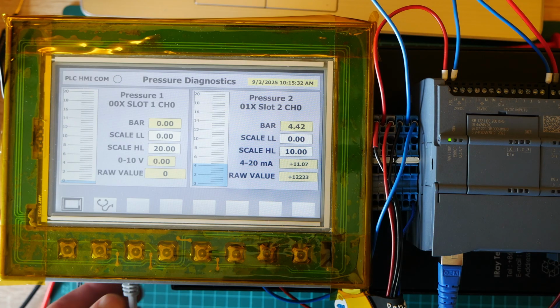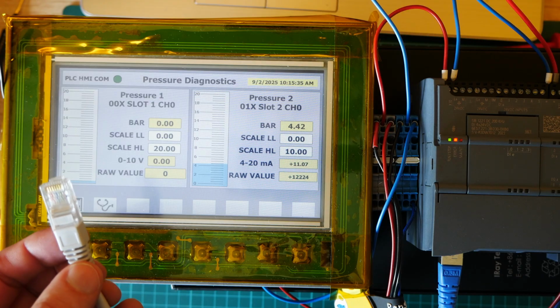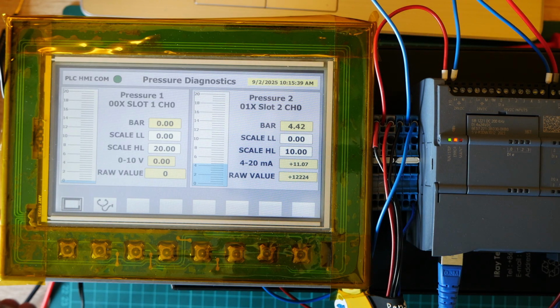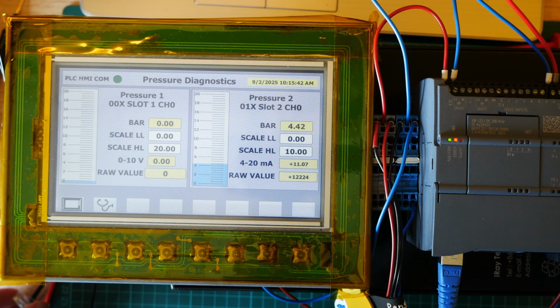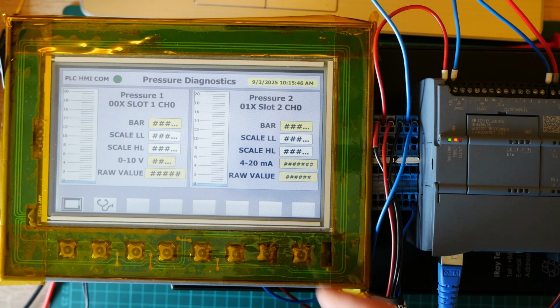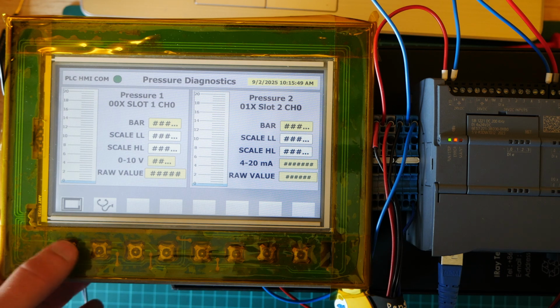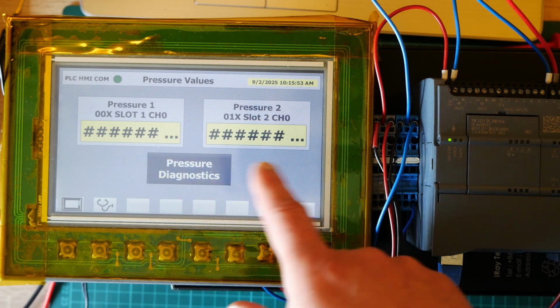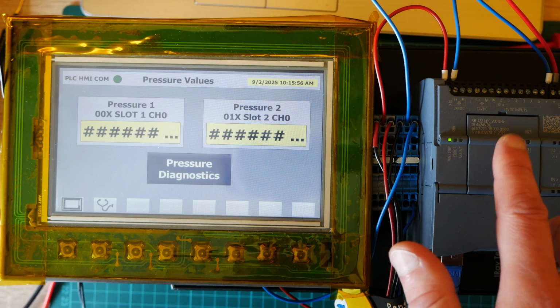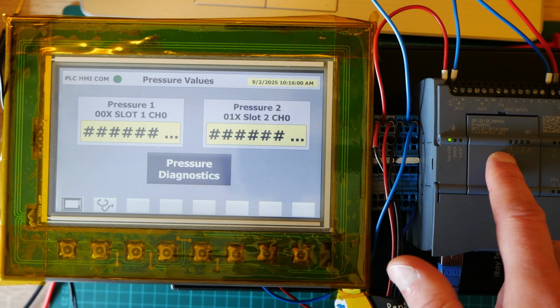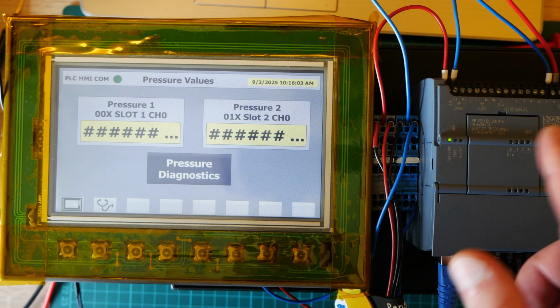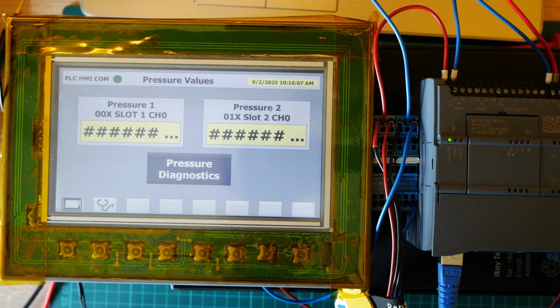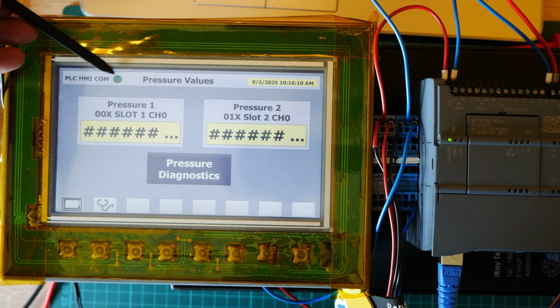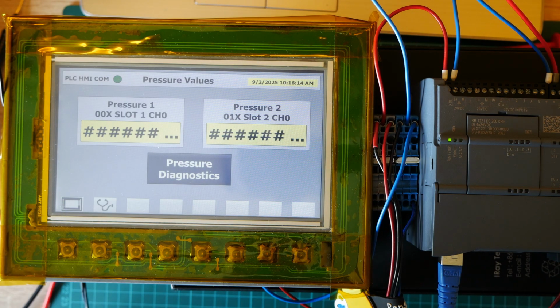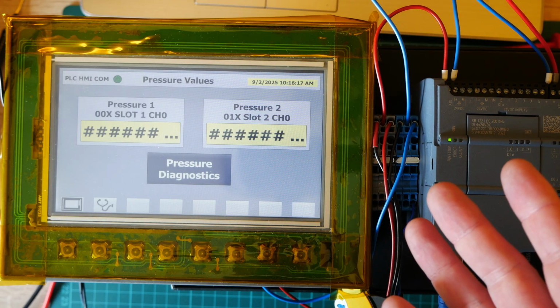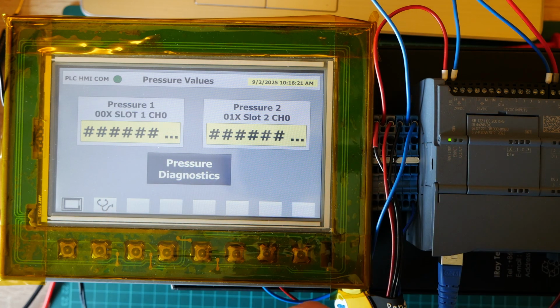And for a communication error, okay, I will remove the communication cable in the HMI, and it takes quite some time to actually show it. So yeah, right now on all screens you have these hashtags, okay? So this is a communication error. And usually what I do, from the PLC I just use a clock of 500 milliseconds, and it triggers a boolean, a bit. And this bit is shown here, PLC HMI communication. If this blinks, then it means communication is okay. If this doesn't blink, well, we have issues with communication.